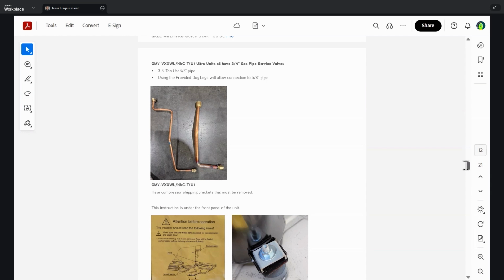These dog legs actually let you connect at the service valves and come outside of the cabinet. That way you're not having to do any of the ratchet bending or fittings. And each outdoor unit comes with these, so they're from the factory. They're not anything additional.